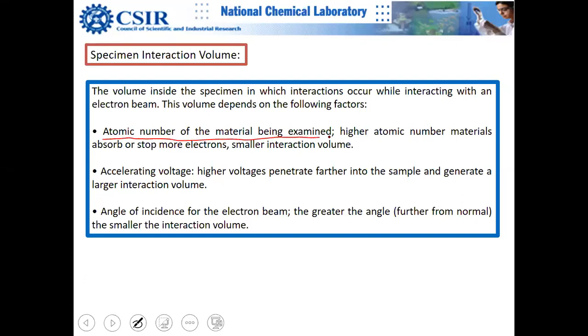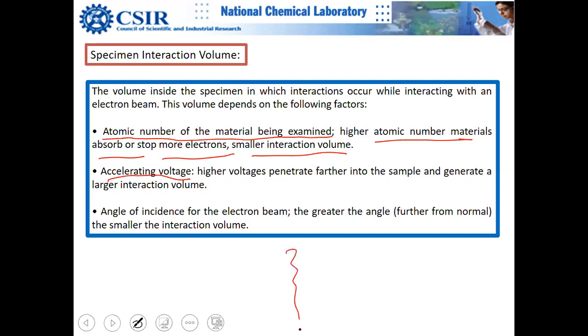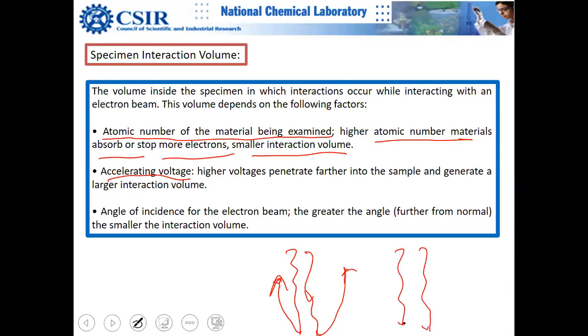Three key factors affect sampling depth: atomic number of the material being examined — higher atomic number materials absorb or stop more electrons, giving a smaller interaction volume; accelerating voltage — higher accelerating voltage allows electrons to penetrate much deeper.